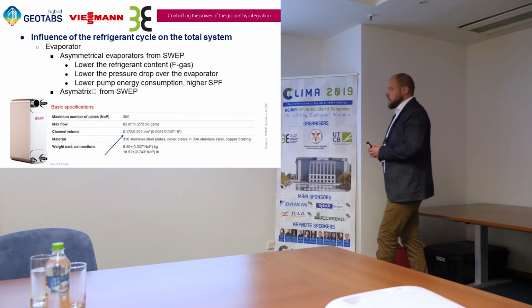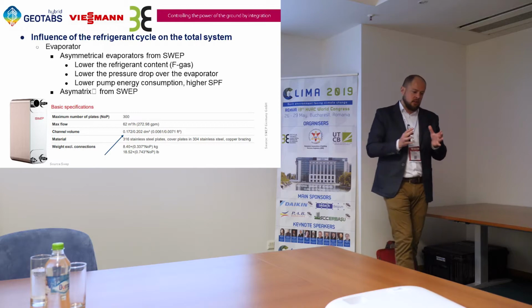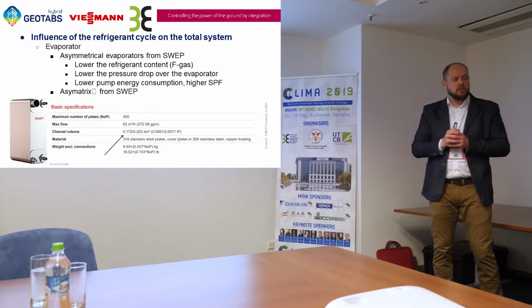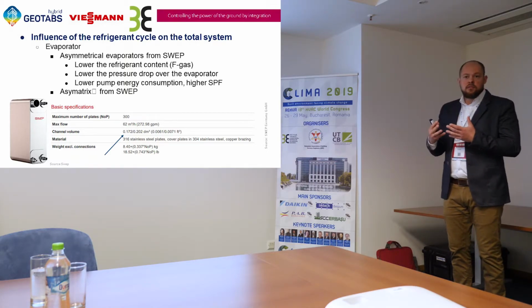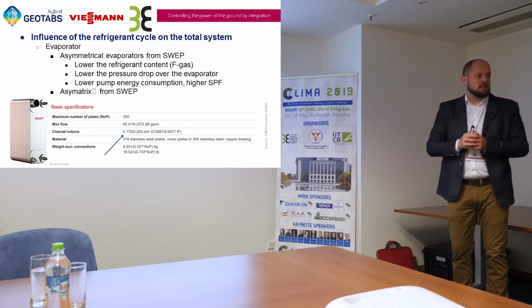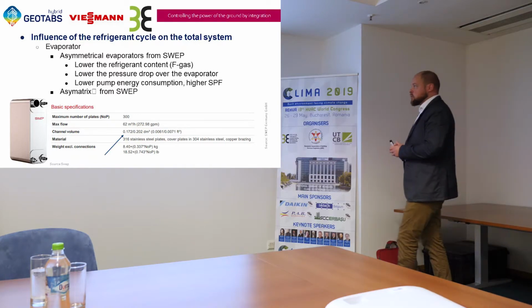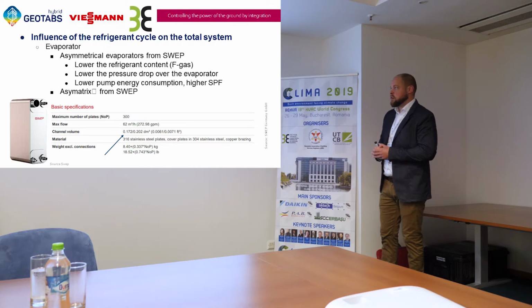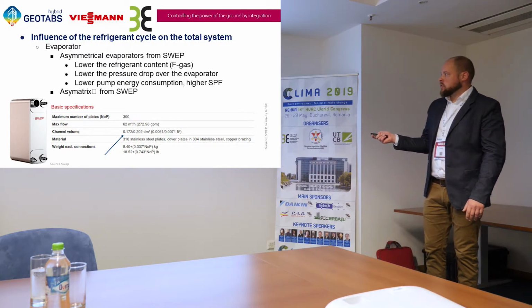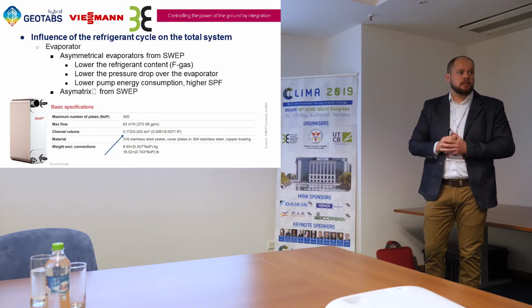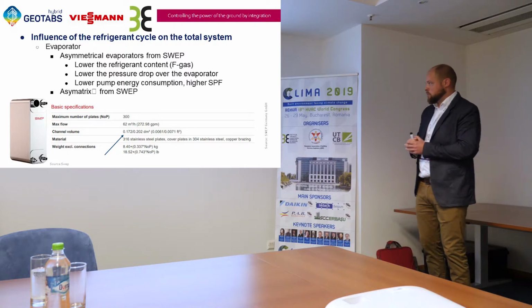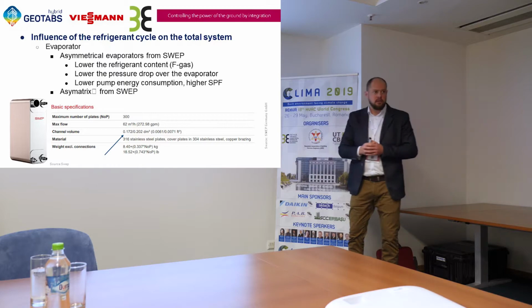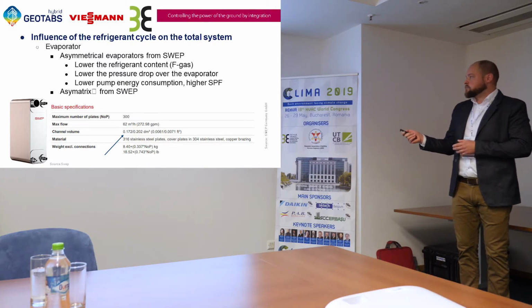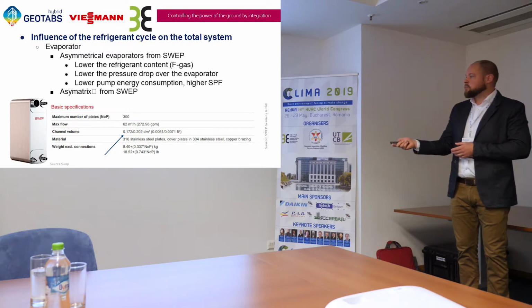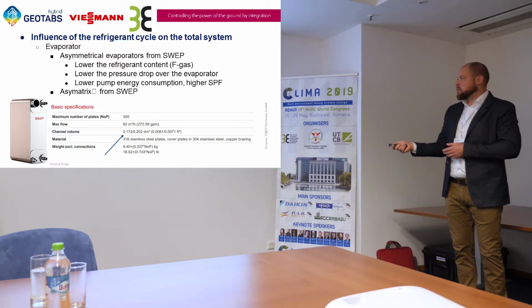What we also see today is that we use asymmetrical evaporators. This means that the size on the refrigerant side is much smaller than the size on the liquid side. That is also a benefit to the total refrigerant load inside the heat pump, inside the refrigeration cycle. And that's a good thing for the F-gas regulation. We use less refrigerant, so the GWP of the total heat pump is lower. That also means that we have lower energy consumption of the primary pump, because the flow through the evaporator will be easier. The spacing between the plates is bigger, so it will flow much easier. And that effect is even bigger when we use glycol, because it has a lower flow rate. So that's a development that we see today. You can see the channel volume on the refrigeration side, and you can see the channel volume on the water side.